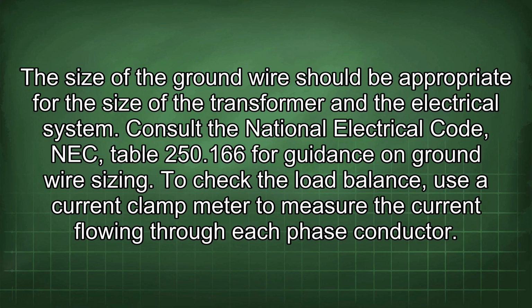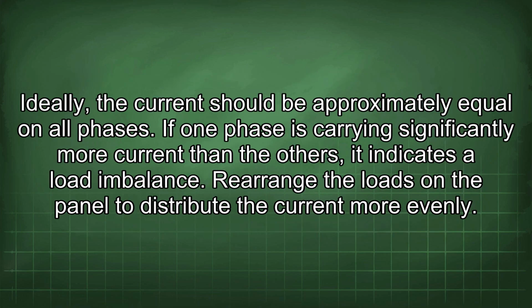To check the load balance, use a current clamp meter to measure the current flowing through each phase conductor. Ideally, the current should be approximately equal on all phases. If one phase is carrying significantly more current than the others, it indicates a load imbalance. Rearrange the loads on the panel to distribute the current more evenly.